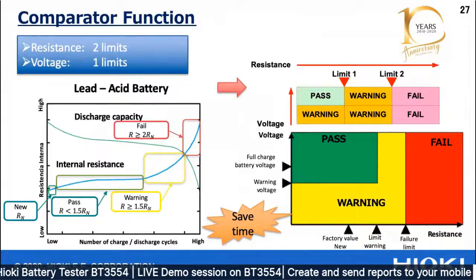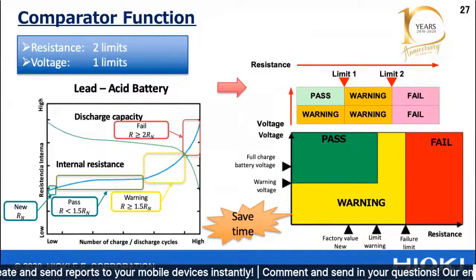During battery operation, the resistance value increases over time. It will be in good condition when showing a pass, meaning the measured value is less than 1.5 times the reference value.